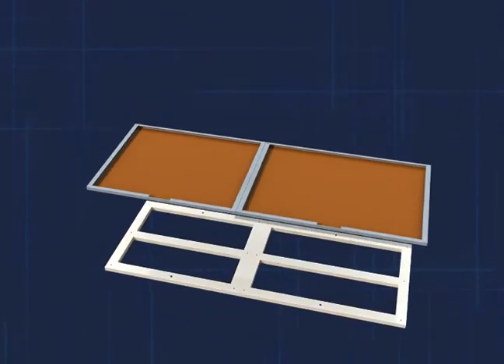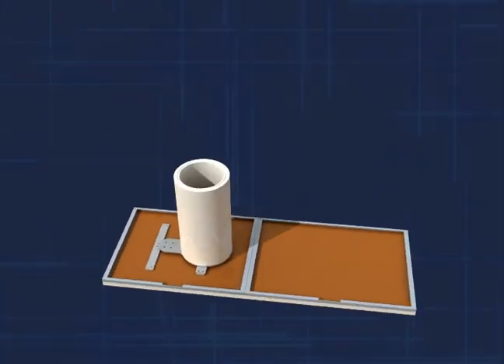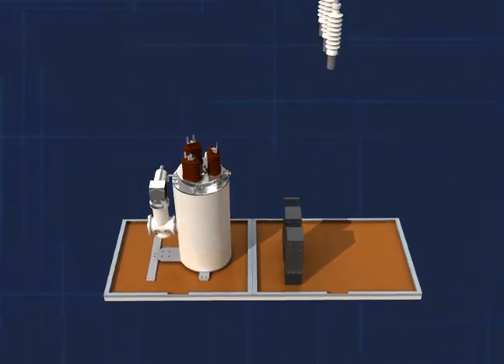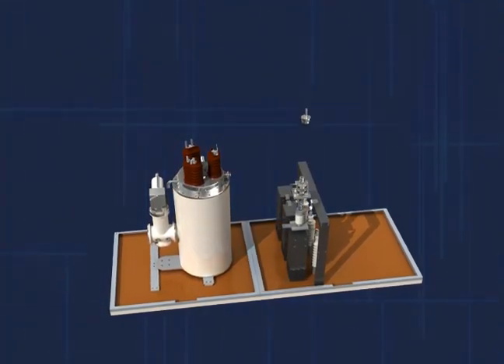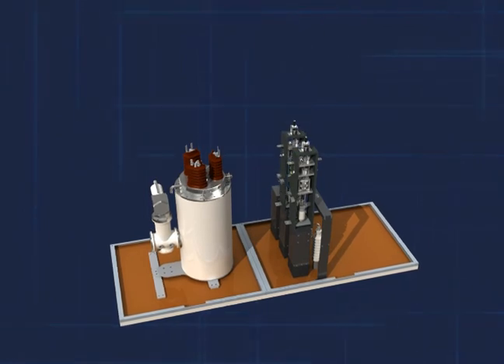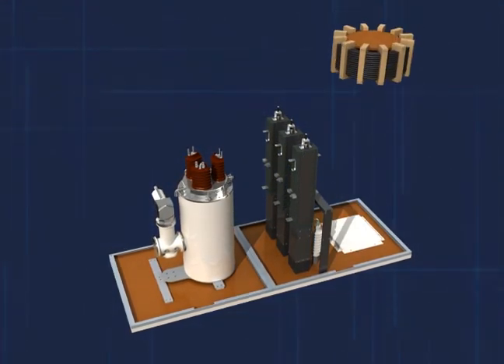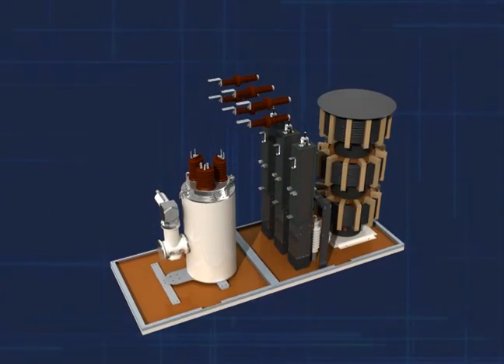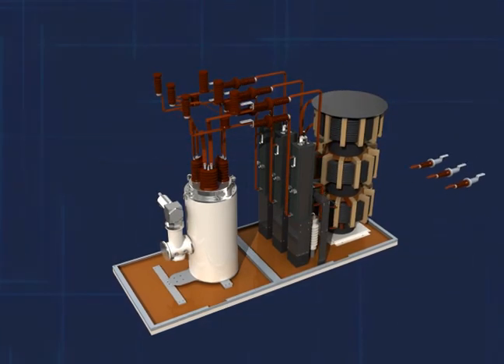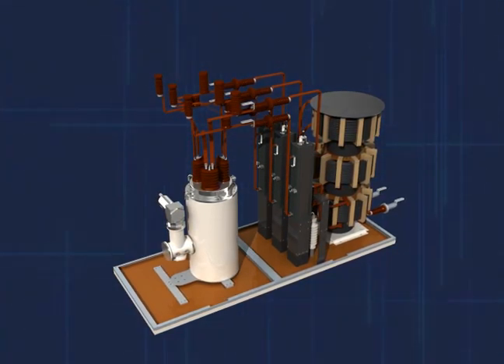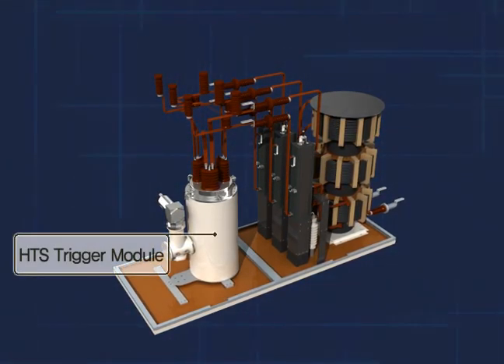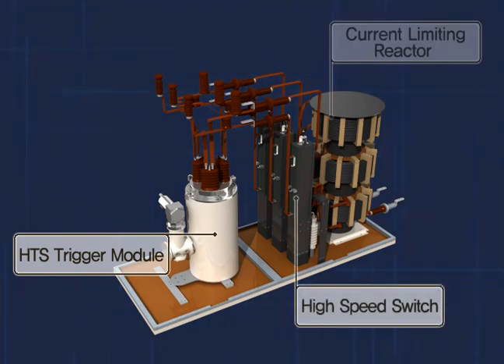A superconducting fault current limiter is a new type of power application which functions as a transient overcurrent suppressor when a fault occurs in a condensed power network. But there are negligible power losses during normal operating conditions when it is added. The superconducting fault current limiter is composed of an HTS module, high-speed switch, and a current limiting reactor.